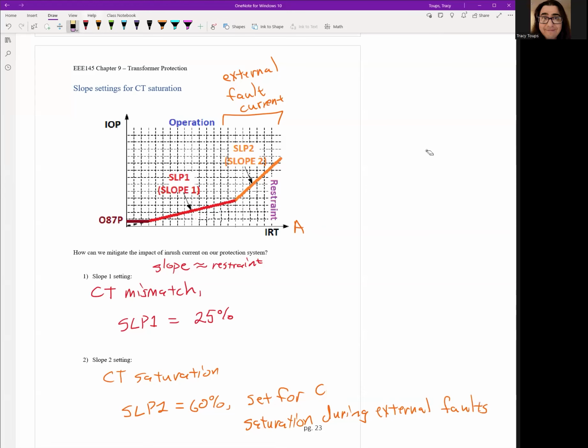Note that for an internal fault, the current is going to be so incredibly high that we're going to overcome the 60% anyway. If you remember, last class period we did an example problem where an external fault without CT saturation showed maybe a 20% slope, so we were fine. For an internal fault, your I operating over I average, that percentage is 200%, which is much higher than 60%, so it would trip anyway. Okay, so coming back to our graph, just remember, anytime we're on the top half of this graph right here, this is the trip region.